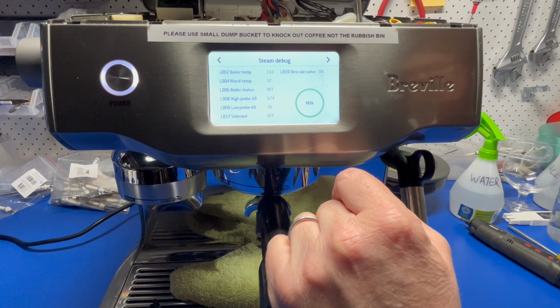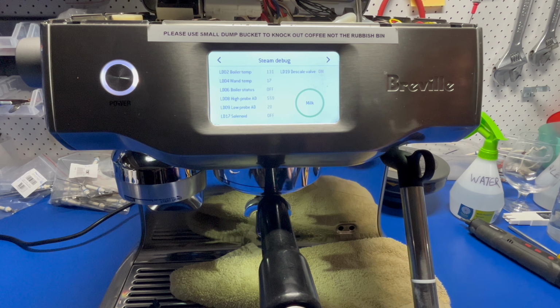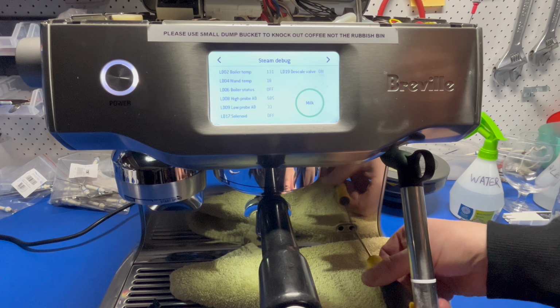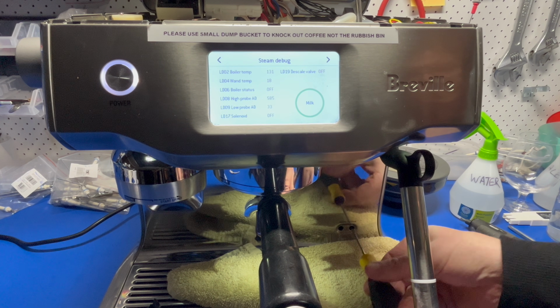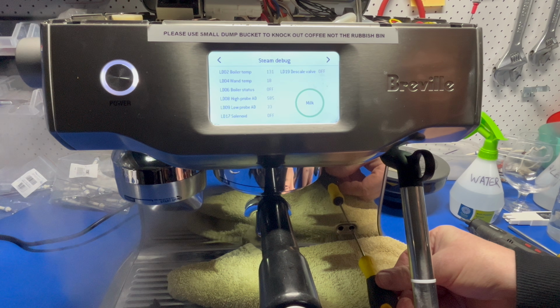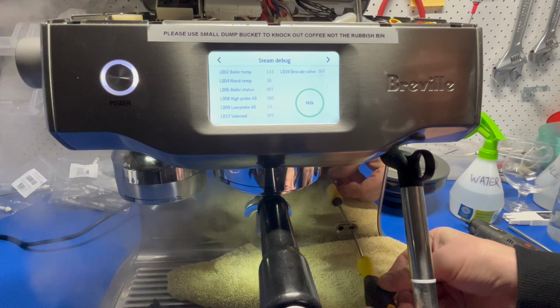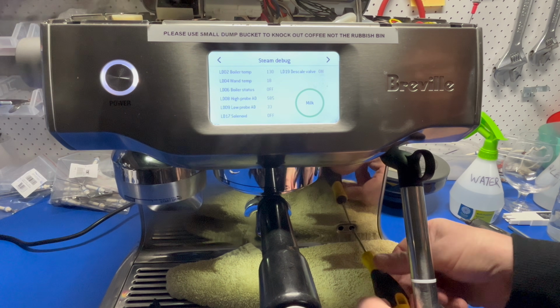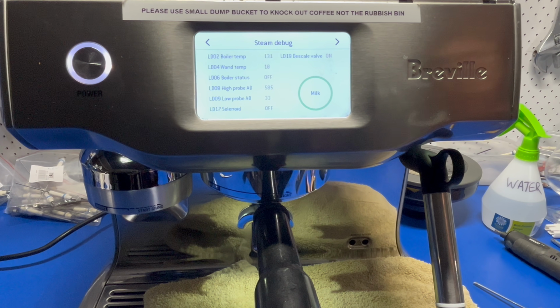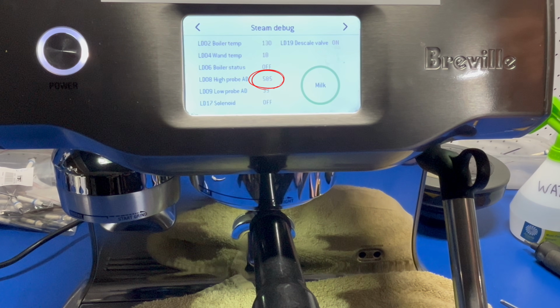What we're going to do now is drain the boiler for around 5 seconds or so, which should be enough to drop the water level below that upper probe, and we should be able to see that on the reading. You can see on this one the numbers actually barely moved, so this would certainly fail a descale.